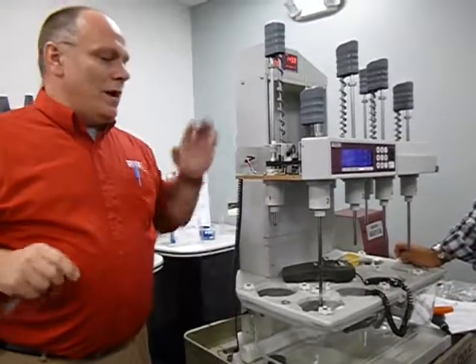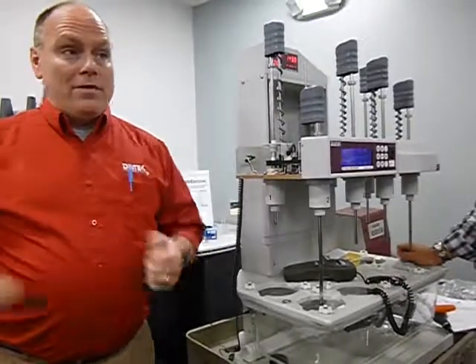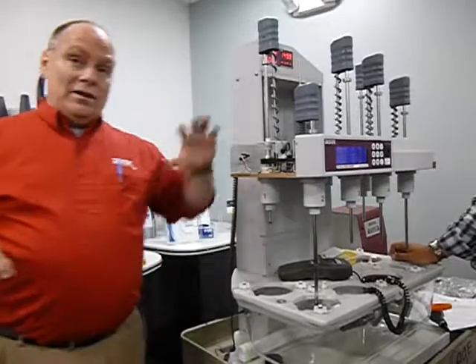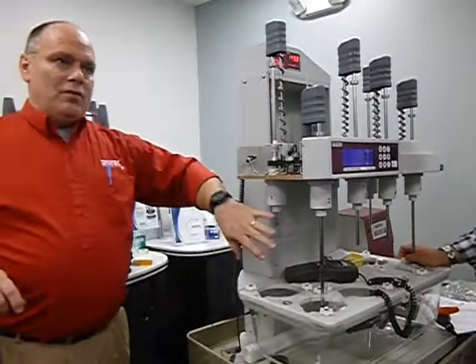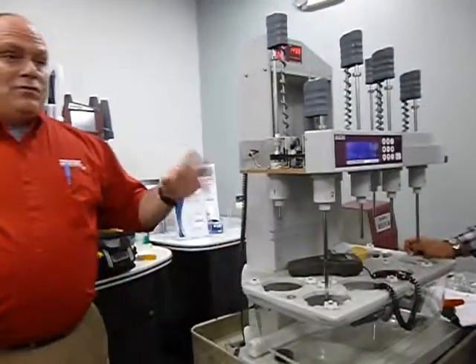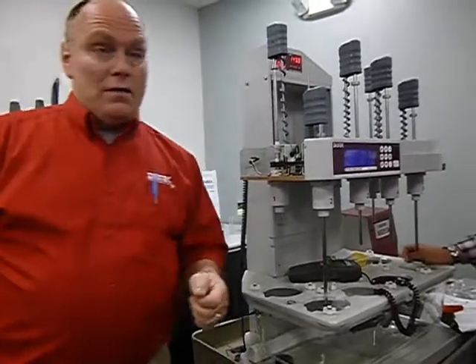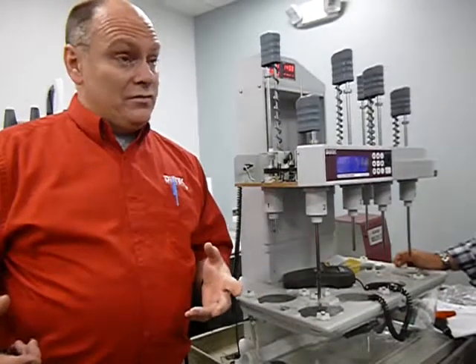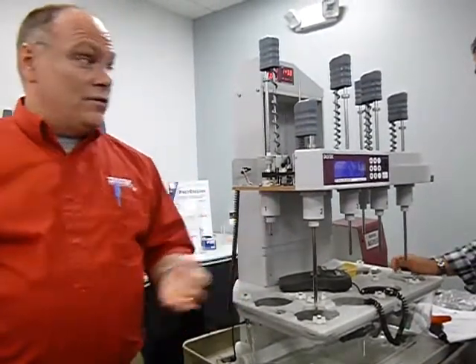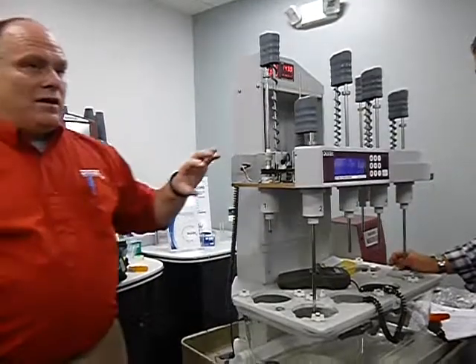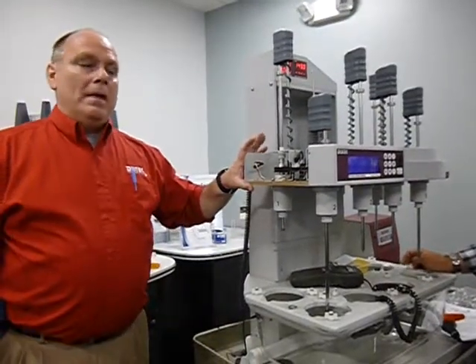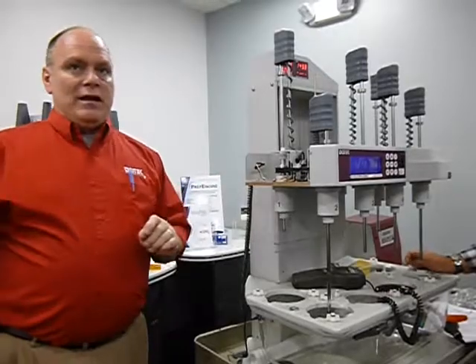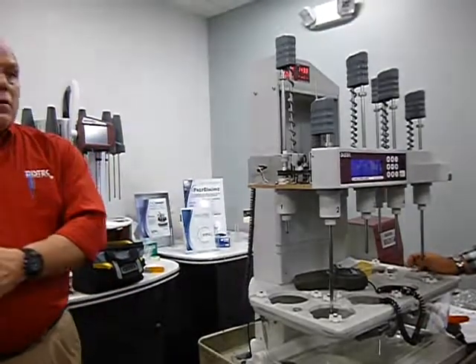The reason being, the way this operates, and the way all of them operate that have RTD shafts, it's electronic in nature. This isn't a true thermometer that's on there. It's an RTD. What it does, it measures the change in resistance of the media. The hotter it gets, the change in the resistance increases. So that's how the RTD works on this. So what it does via a programming algorithm, it'll plot. So what you're doing is you're telling it at whatever degree. Say you had it at 18 degrees Celsius.